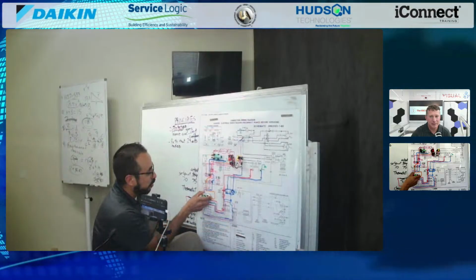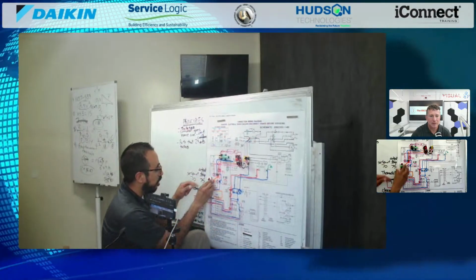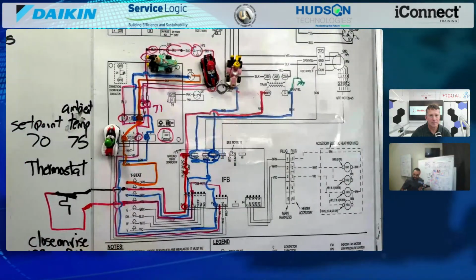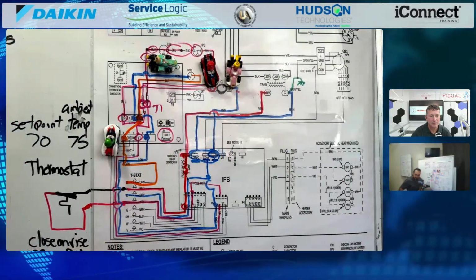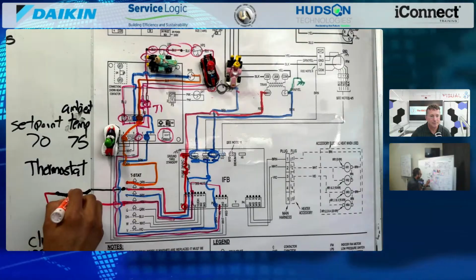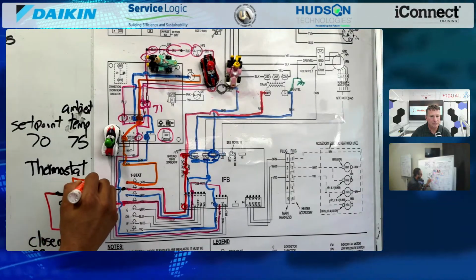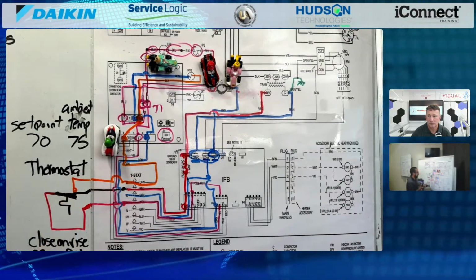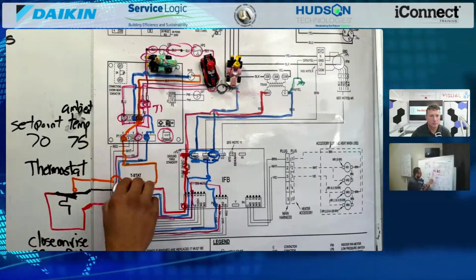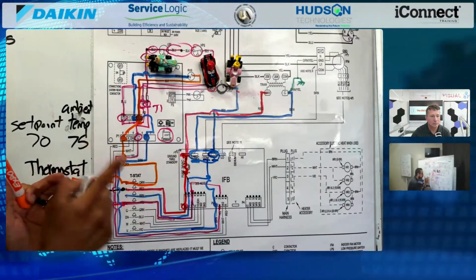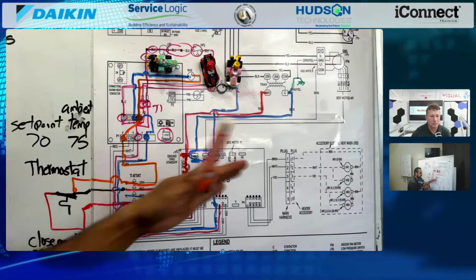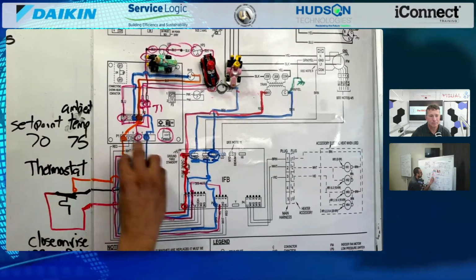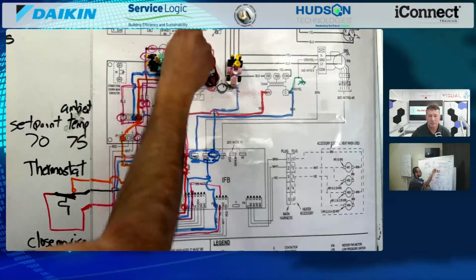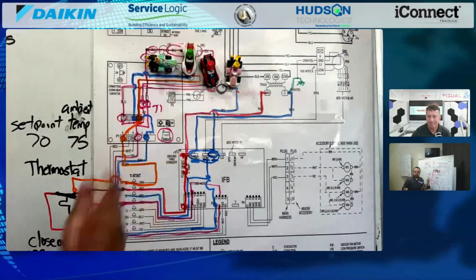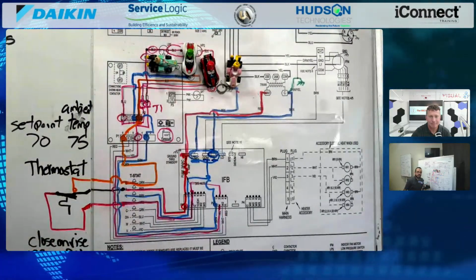So Luigi's gonna go, I have a call for cooling. What happens is internally from the thermostat, it's gonna give the 24 volts, so it really starts here with 24 volts. Thermostat has 24 volts: hey, you have a call for cooling? Here you go, reversing valve, because this is cooling. So it goes, and if you follow it, it goes to the reversing valve. Now the reversing valve has 24 volts, and I have a call for cooling.